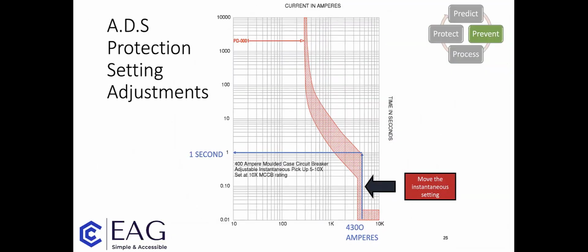The next thing is what I call the low-hanging fruit of arc flash management, and that is looking at protection coordination and protection settings. From my experience, by moving the instantaneous setting, if we've got, for instance, 4,300 amps, which is taking a second to actually clear, if we're able to move the instantaneous setting, that same 4,300 amps may look more like 0.02 seconds. That happens to account for probably 90% of actions to prevent injury and damage.